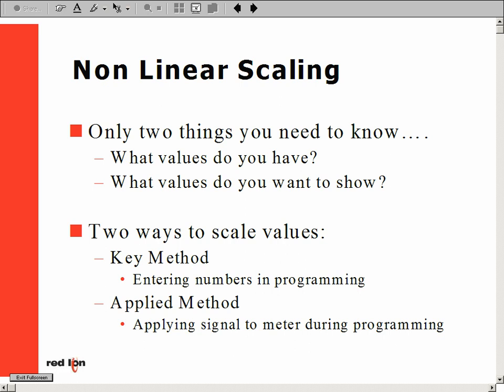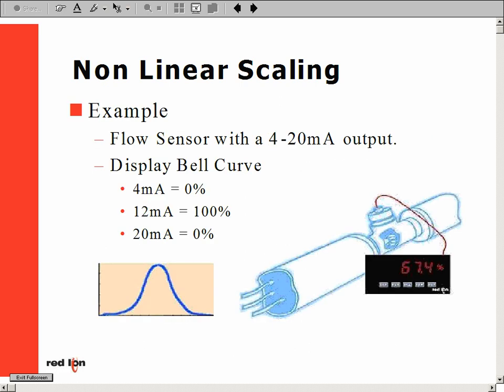The first step is to select the proper scaling method — key or apply. The next step is to key in or apply the low input signal. In our example, that would be 4 milliamps. Next, in step 3, we key in our corresponding display reading for the low point, which is 0.